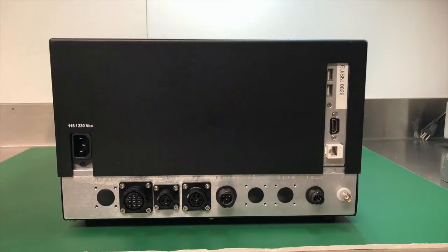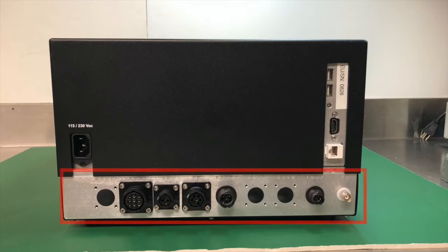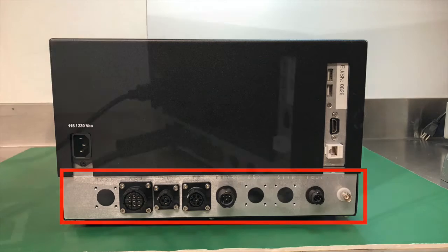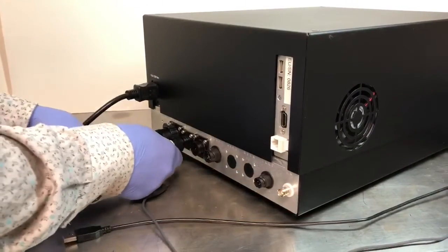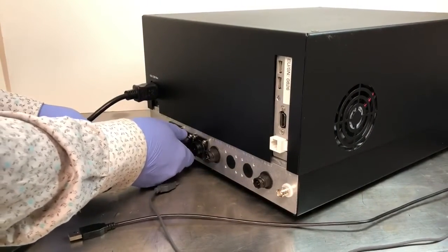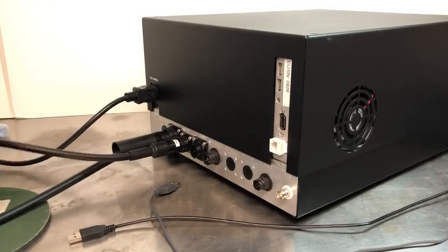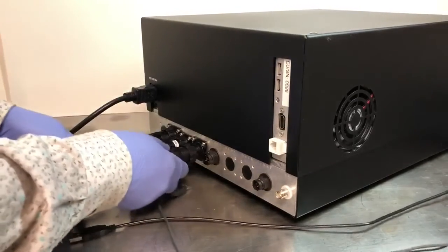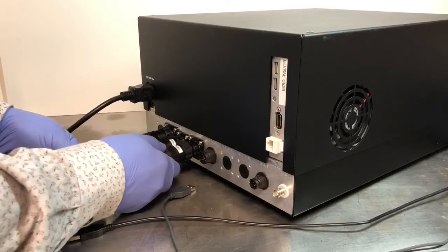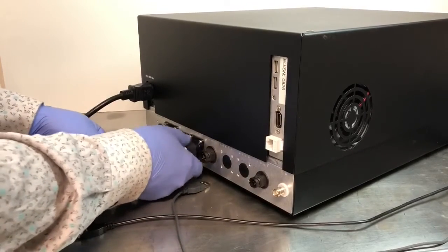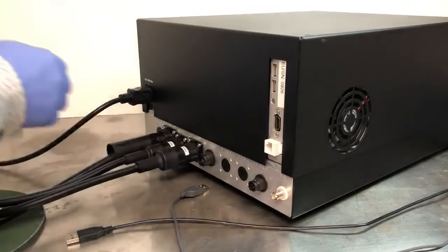At the bottom of the rear of the electronics box are a series of ports for the sensors of the DT-300. The amount of ports here varies depending on the options purchased with the instrument. All sensors can be plugged in by hand, requiring no additional tools. Be sure, when plugging in the sensor cables, to properly align the plug with the port in order to avoid cross-threading. The ring on the plug is turned clockwise until it locks into position. You should feel it click into place when the plug is fully connected.